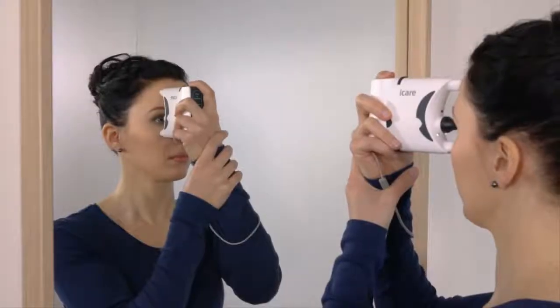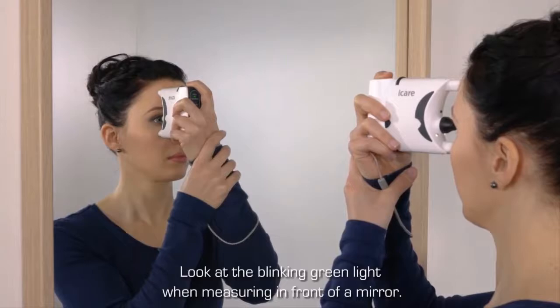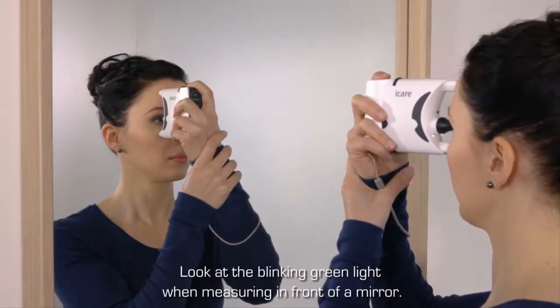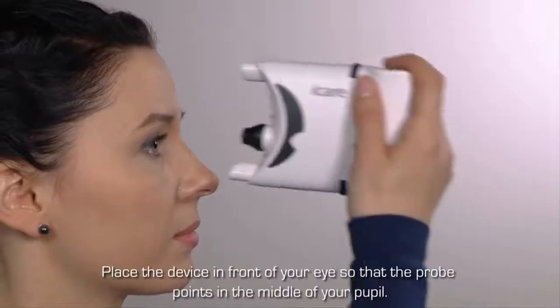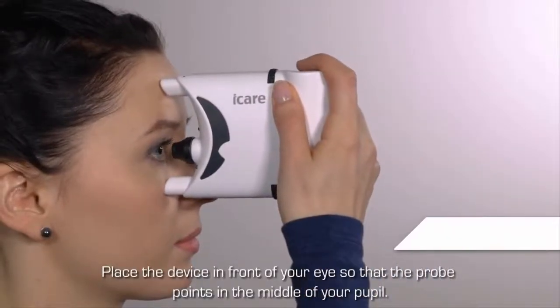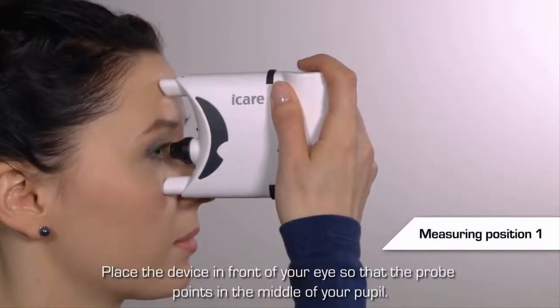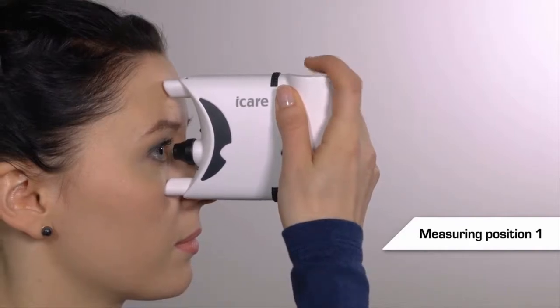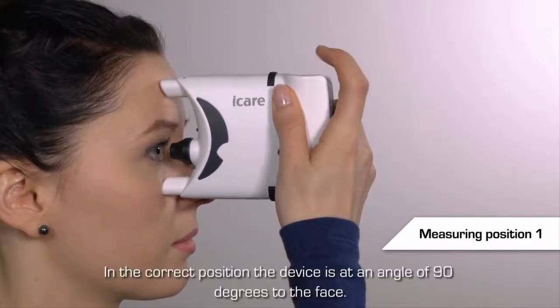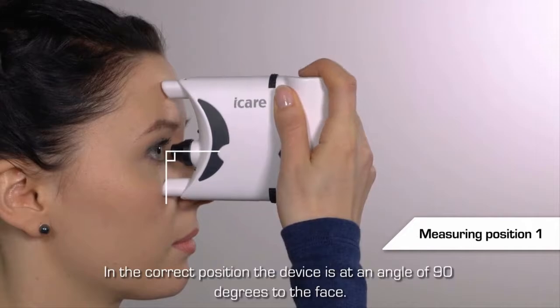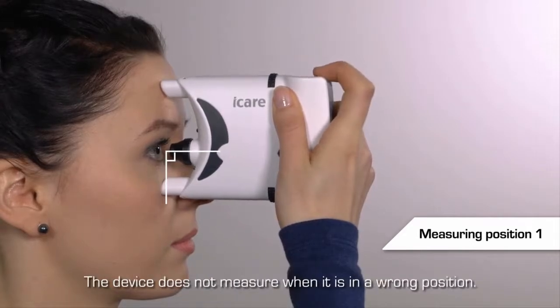Keep a good posture. Looking in a mirror can help with positioning. You can see the flashing arrow light in the mirror. Place the device in front of your eye so that the probe points in the middle of your pupil. You'll see a symmetric circle. Keep the tonometer at an angle of 90 degrees to the face. The device is in the correct position.